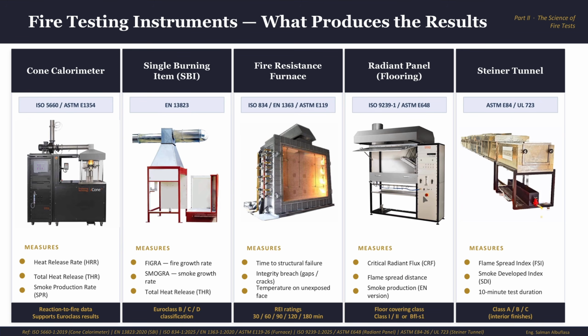The specimen is ignited at the hot end. Flame travels along the surface, and at some point the heat is no longer intense enough to sustain the flame. It stops. The machine records exactly where it stops. And we extract a critical radiant flux value from this, not pass or fail, a number. The higher that number is, the harder the material is to ignite and sustain flame spread.